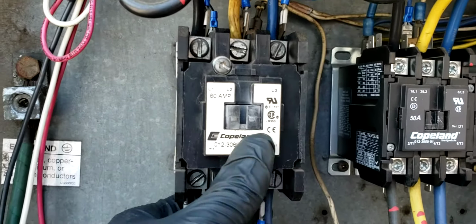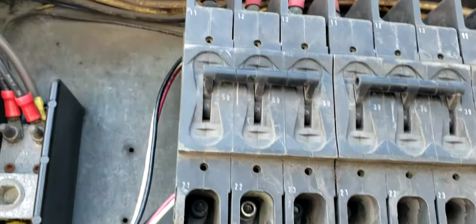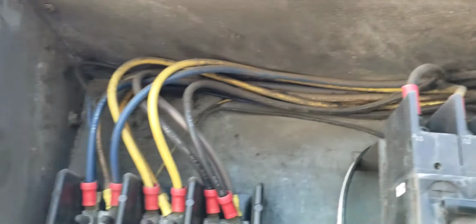Let's say this was contactor number 1. Up top here is where the power comes in. Right here is the main power. It comes in right here. And let's just say this is line 1, line 2, line 3, and you bring it accordingly. Line 1, line 2, and line 3 on your contactor for contactor number 1, for the part winding.